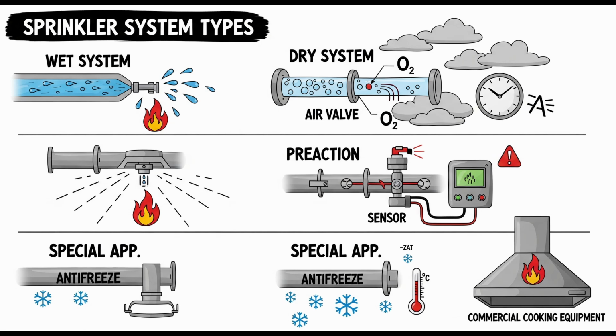All fuel, all heat to all protected equipment under that hood shuts off automatically when any part of the system activates. Yes. And furthermore, any other gas appliances that might be located under the same ventilation hood but perhaps didn't require dedicated protection must also be automatically shut off. Critically, all these fuel and heat shutdown devices, valves for gas, contactors for electricity, must require manual resetting. They cannot automatically restore power or fuel flow after the fire event.